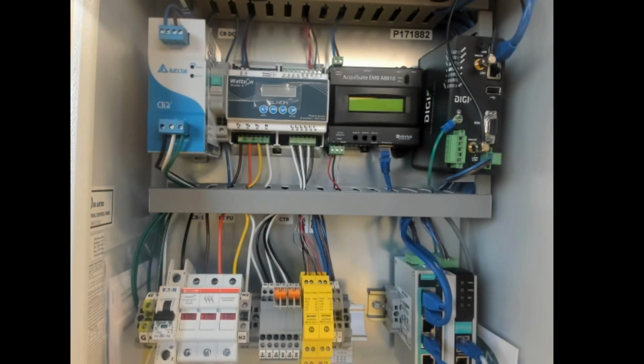One of the things you'll notice right away is that we have a different power supply here. As many of you know, we've had issues with the robustness of the Schneider power supply — a lot of DOA units, and units failing after commissioning. We've communicated these issues to Schneider but haven't had great feedback on next steps, so we've decided to move away from Schneider entirely. DST recommended this Delta CliQ II model line, which they have great experience with. All power supplies look pretty much the same on paper, so it's helpful to know anecdotally that they haven't seen any failures from Delta like they've seen from Schneider.